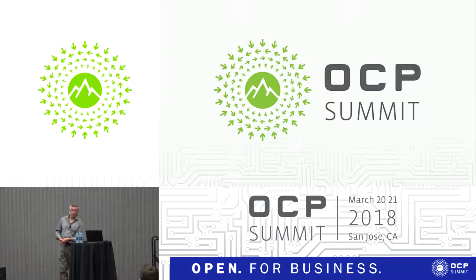No, absolutely not. The rectifiers are set up so that they will work. The controller is a field replaceable unit as well, and you can unplug it, and the shelf will continue to produce power exactly the same as it always has. The only detriment will be that it may not share power between the individual modules quite as well. Current sharing is degraded very slightly, not enough to affect operation though. Each of the modules continues to work at its most recent set point.